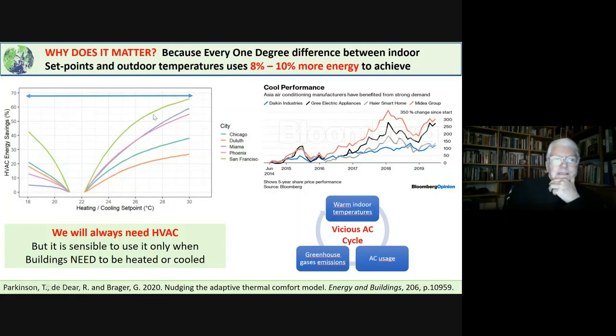So for instance, in San Francisco, if you set the cooling set point at 22, which many buildings are set at for summer, when it's perhaps 28 or even 30 degrees centigrade outside, you can save 65 to 70% of HVAC energy. If you set the set point at 28, or allow the building to roll up to 28 internally, you're saving 60% of the summer cooling energy you need. And in winter, in San Francisco, you can save 40%.